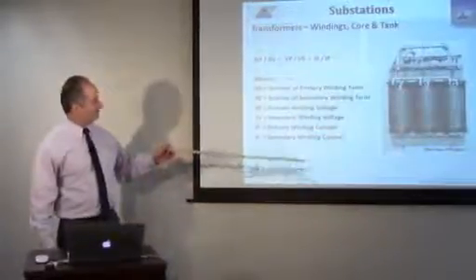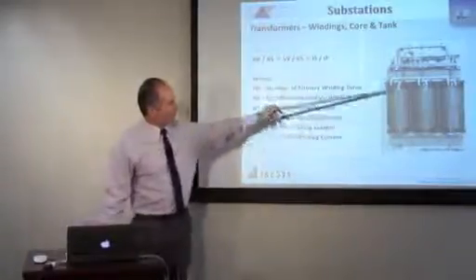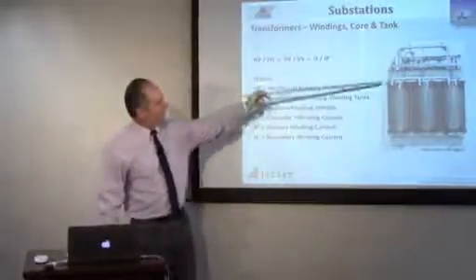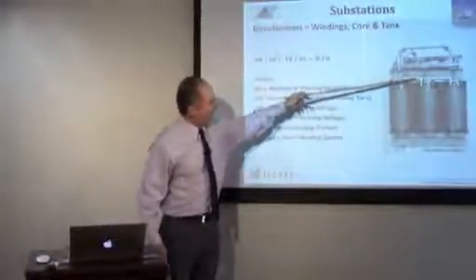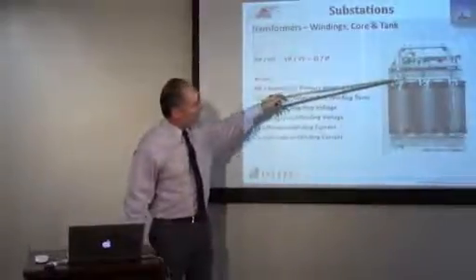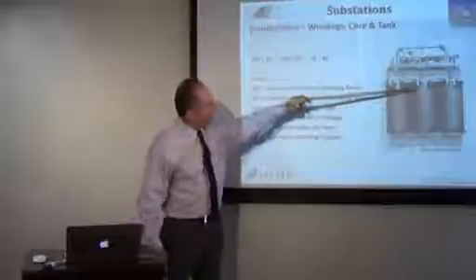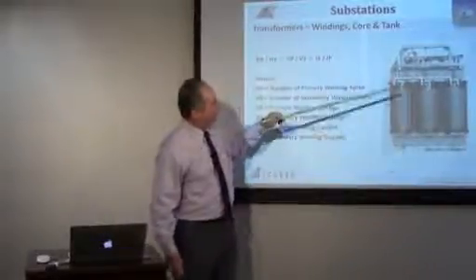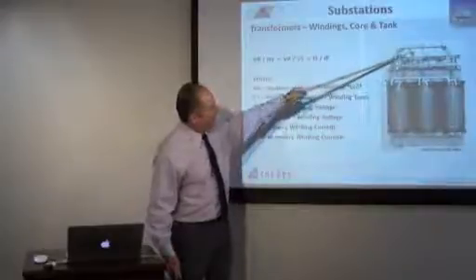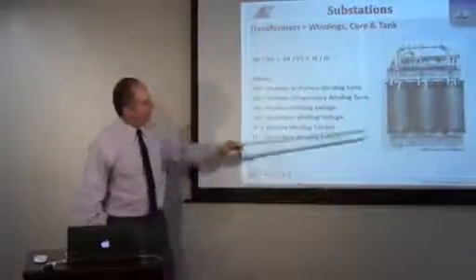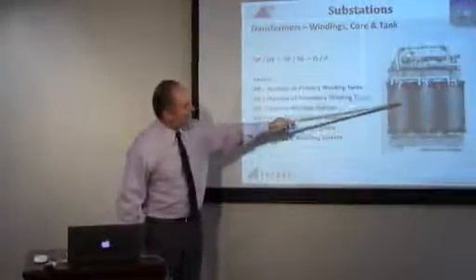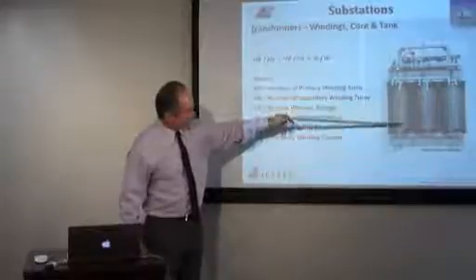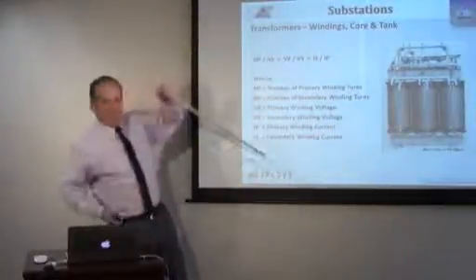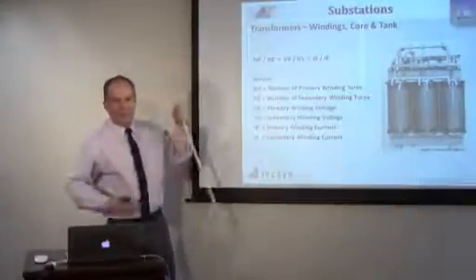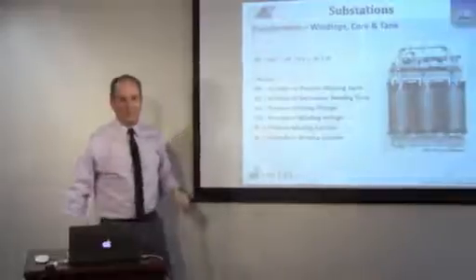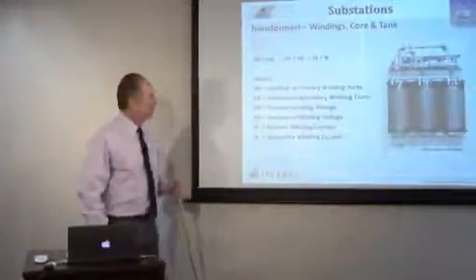But here, inside the transformer, we have coils like this. You can see the solid conductor here. That would be for a common Y or a neutral. We have a grounded Y, so each phase, and then the neutral. And then we have the high voltage windings inside with their wire, going up to their own bushings. So basically inside a transformer we have all these windings. The windings are spaced with little spacers. And when there's a fault, they like to stretch like a spring. And if you fault the transformer too much, you lose some of those spacers and they fall out on the bottom and you don't even know it, and you can have a transformer failure the next time because the windings move a lot.